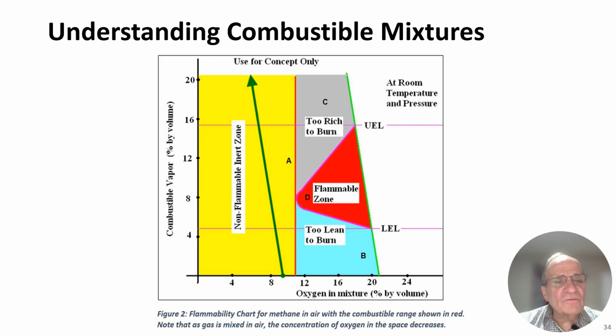Here's a graphical representation of the fuel gas mixture in a room. Let's say I have a room and it's filled with 100% air. Well, I got 21% oxygen. As I start to add gas to that room, the oxygen content decreases because I'm now mixing the air in the room with a certain amount of fuel. In this case, I'm mixing methane. I get up to 4%, and I'm still not at a point where ignition will take place. There's too much air in the room for ignition to take place.